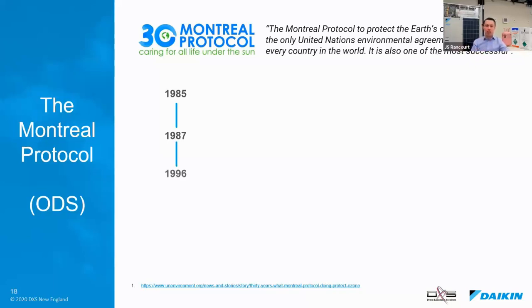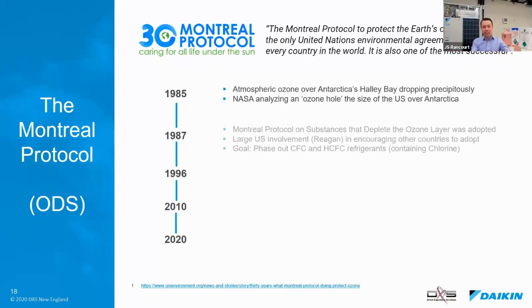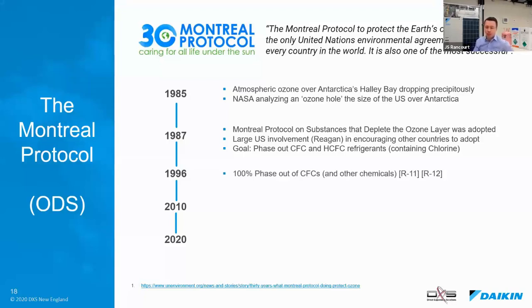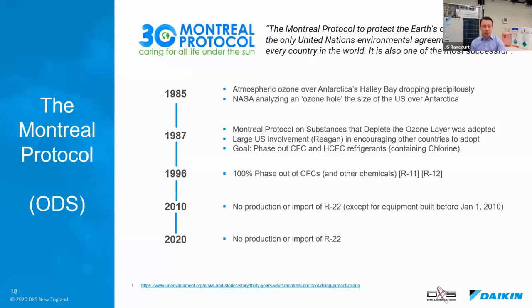So starting back in 85 is when scientists started noticing a depletion of the ozone layer in a hole the size of the United States above Antarctica. By 87, the Montreal Protocol was signed specifically targeting chlorine-based refrigerants, CFCs and HCFCs. At the time, the United States had a huge involvement. They were a cornerstone in ensuring that every country in the world was ratifying it under the Reagan administration. By 1996, 100% of CFCs were phased out. Those are the real dangerous ones for the ozone. So it took only 8 years to get those completely out. By 2010, the limitations on HCFCs meant that manufacturers stopped building equipment using R22, although you could still buy it and make it for old equipment. And by last January was the official end of R22 production or import into the U.S.